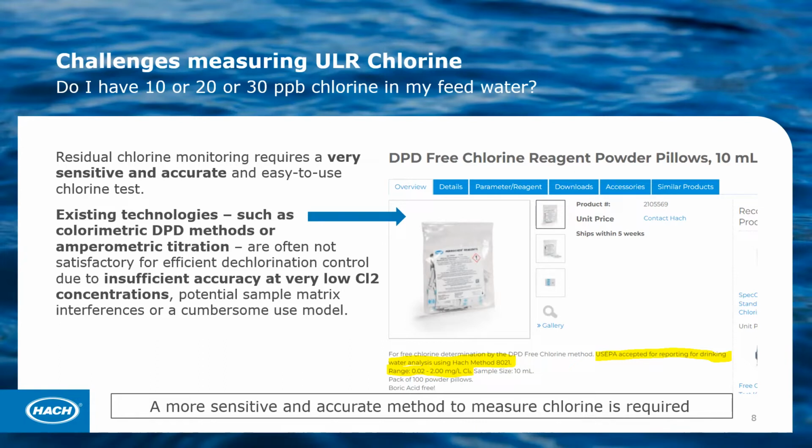It's difficult to detect, it's difficult to create stability in our testing environment, and those common solutions that we're used to, sort of the tried and true methods for chlorine monitoring, are very good at what they do in the range that they're intended for. However, when we start trying to push those limits of what they're intended for and measuring either higher or lower, then we really need to be aware of the limitations of existing technology.